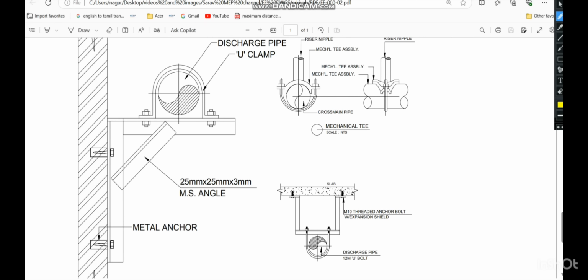Additionally, this gives the detail of pipe support through the wall. Sometimes we provide the pipe support from the side of the wall. Like you can see, you have to provide the metal angle like this, and the MS angle has to be provided with 25, 25 and 3 mm. And the discharge pipe with the U clamp is provided here. So this is only for the pipe support through the side of the wall.